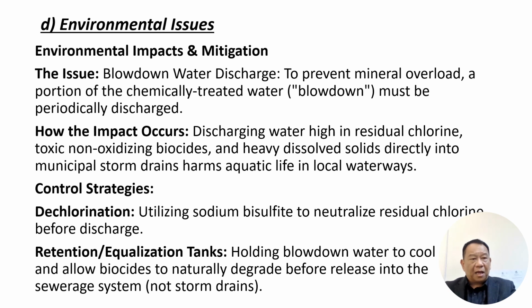We also face some environmental issues. Environmental impacts and mitigations. The issue here is blowdown water discharge to prevent mineral overload. A portion of the chemically treated water blowdown must be periodically discharged. So we discharge it batch by batch. We don't release it in one go, right? The impact occurs when discharging water with high residual chlorine, toxic non-oxidizing biocide and heavy dissolved solids directly into the municipal storm drain, harming aquatic life in local waterways. Actually, this can kill the fishes in the drain.